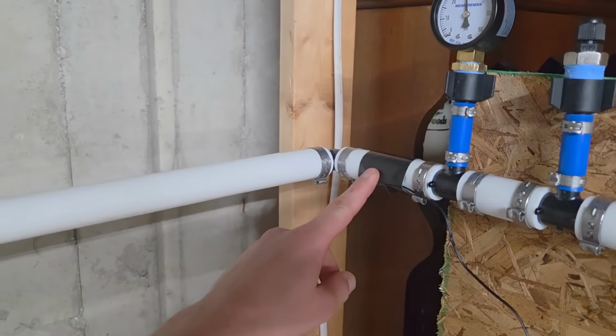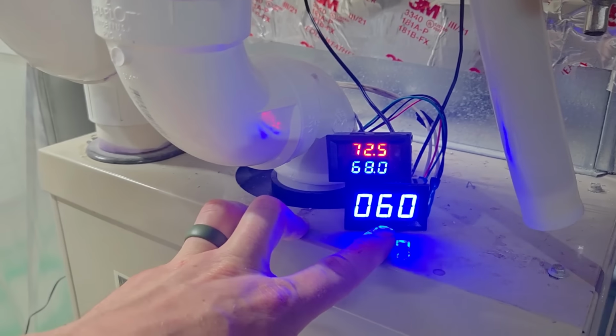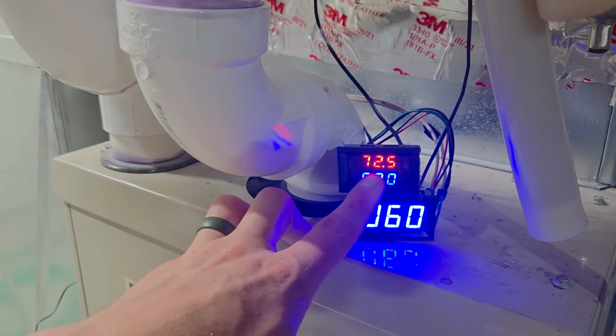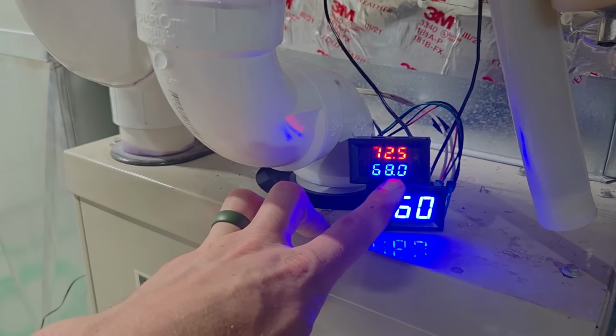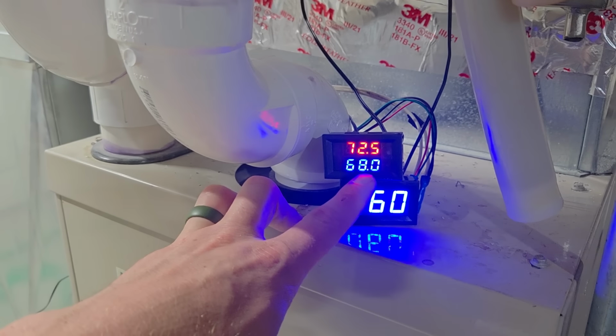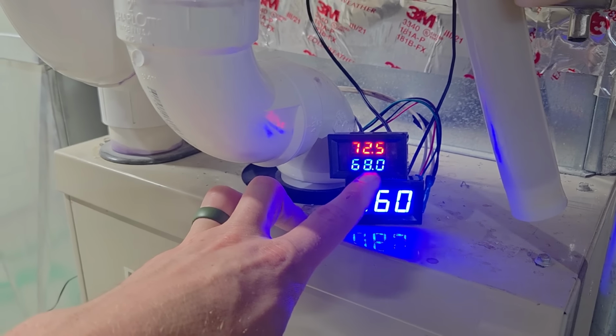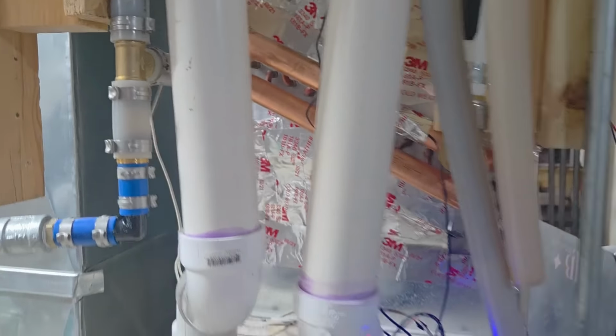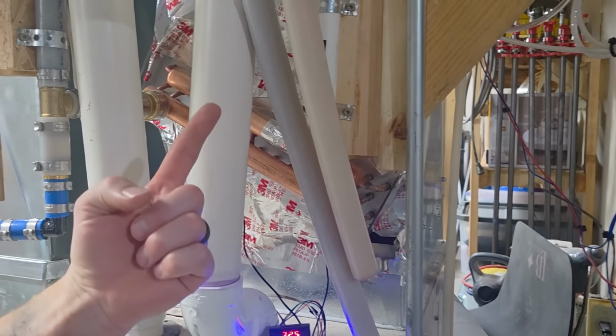Well, I think this is a more accurate measurement because it's taped right onto the copper versus this. It's not a very great measurement because it's taped onto the PEX. 60 degree heat exchanger temp, air temp is 72.5 coming in. After it goes through the heat exchanger, I'm looking at 68. 4.5 degree temperature swing as the air is coming up through the plenum here past my heat exchanger.